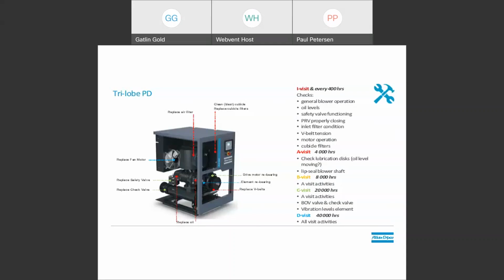We recommend inspecting and checking the check valves annually, just to ensure that the seals are properly sealing to prevent backflow. And you'd also want to replace these units if they're damaged, and if they're not, we still recommend replacing them every 2 to 3 years, just to ensure that they don't become damaged and allow backflow to go through the machine as other machines are typically running. Other maintenance items to the 5-year point would include things like bearing changes, replacing blow-off valves, looking at things like the electronic fans, pressure sensors, and things like that to make sure they're in good working order.